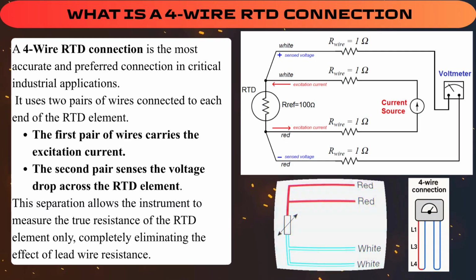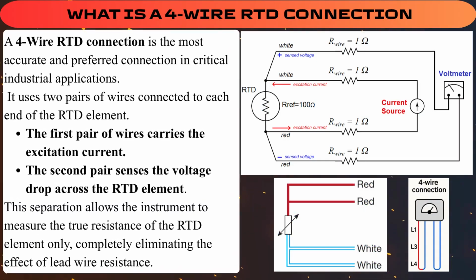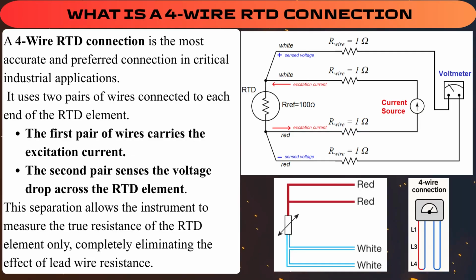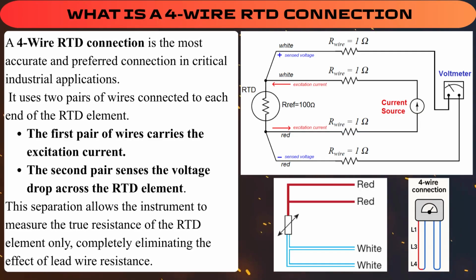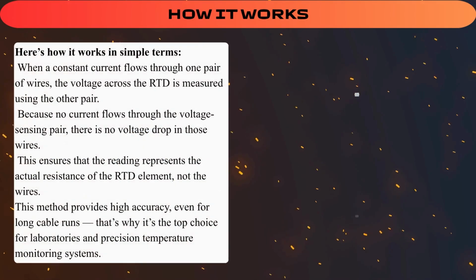What is a 4-wire RTD connection? A 4-wire RTD connection is the most accurate and preferred connection in critical industrial applications. It uses 2 pairs of wires connected to each end of the RTD element. The first pair of wires carries the excitation current. The second pair senses the voltage drop across the RTD element. This separation allows the instrument to measure the true resistance of the RTD element only, completely eliminating the effect of lead wire resistance.